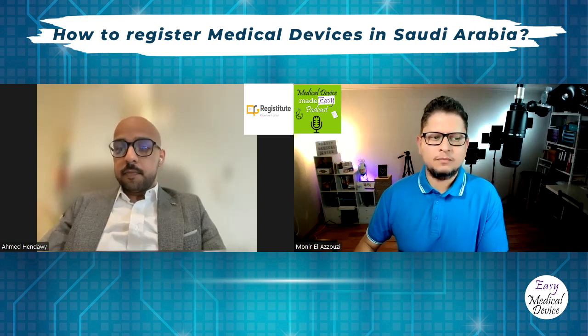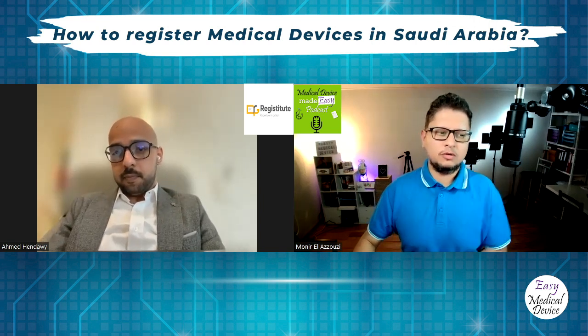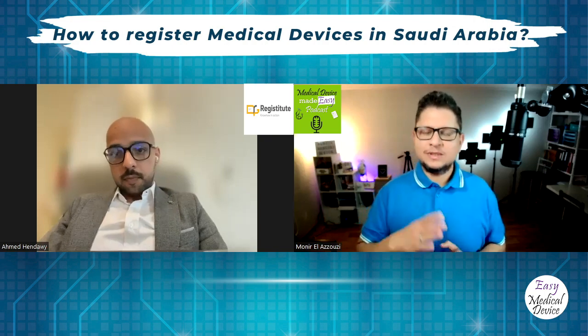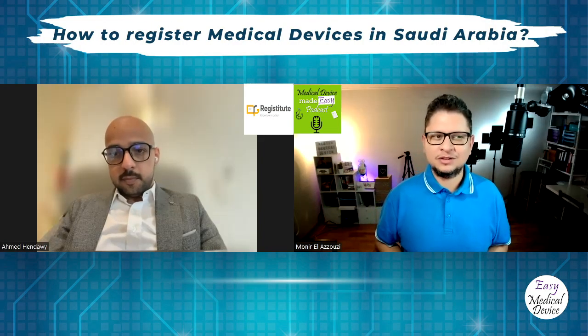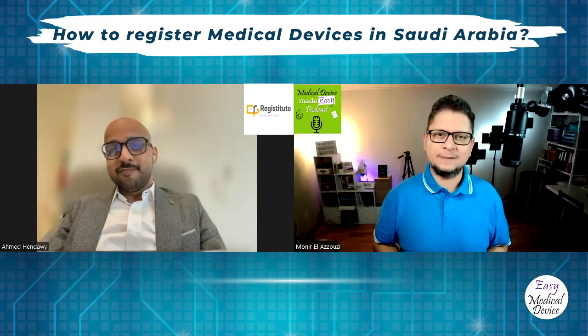Okay, I wanted to ask you another question about medical devices. As we said before, we have multiple classes. In Europe, we have a specific requirement for class one, which is self-declaration, mainly to say I declare that my product follows the legislation, the EU MDR, so I can place it on the market. Do we have this same principle for class one or lower devices? Can I do a self-declaration in Saudi Arabia, saying I am complying with the Saudi Arabia law, and then you authorize my product to enter? Or are there different rules there?